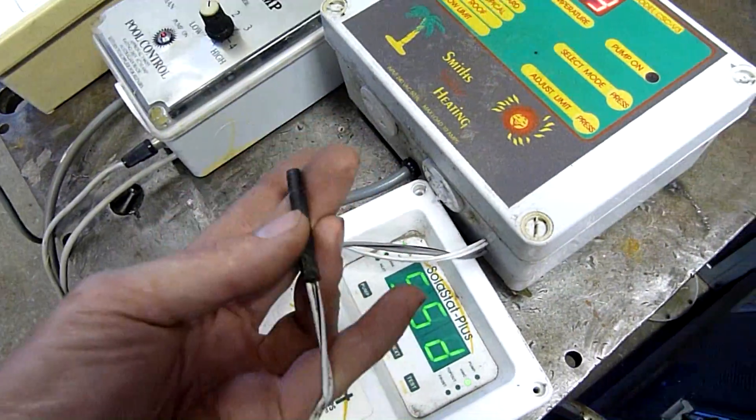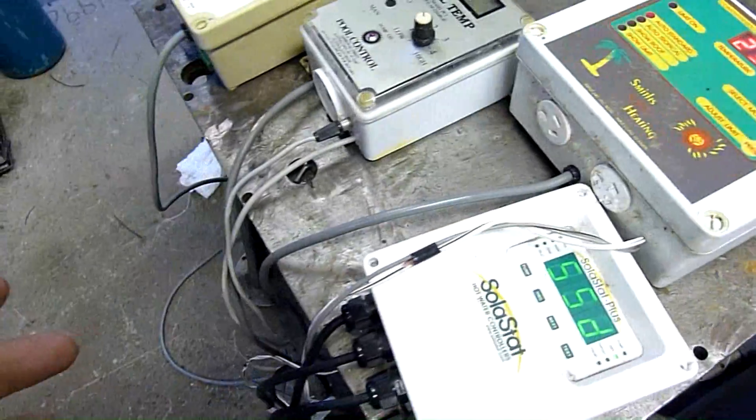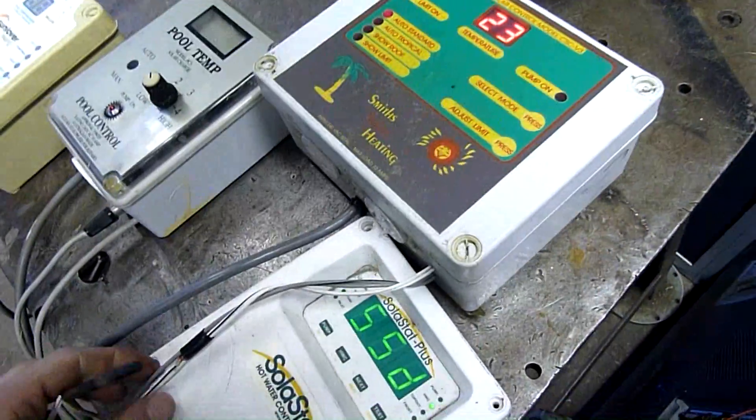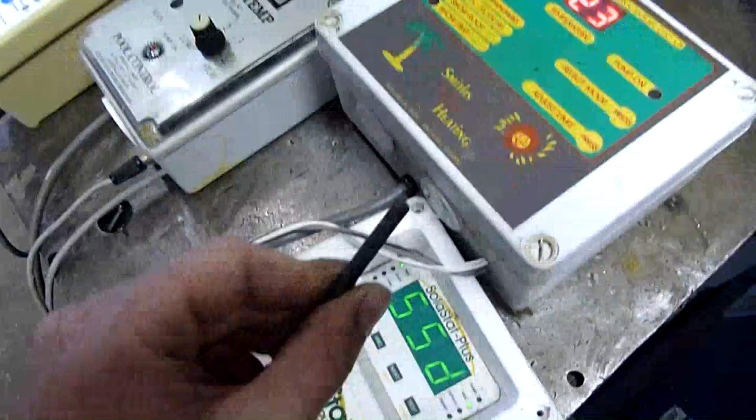It tells it roof temperature, and when the roof temperature rises to a certain point, it turns the pump on. Pumps water through the hot collector tubes and then heats the pool. So right now this is actually reading pool temperature. Here you've got pool temp thermocouple and roof temp thermocouple which is up on the roof. And obviously that one's been cut off and discarded. So this one's actually working.